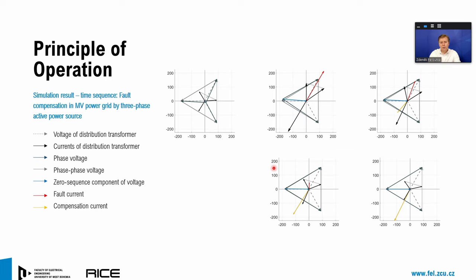How the current source operates. The first figure, which you see here, is the operation of the grid without the ground fault. When the ground fault occurs, we can observe an immediate rise of the fault current, which has, as I said at the beginning, two components, the capacitive one and the active one.